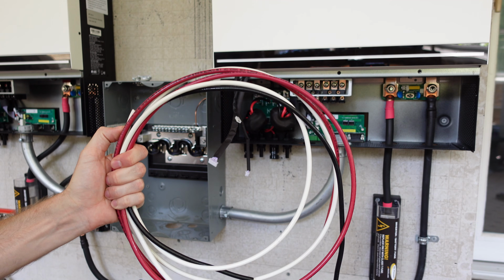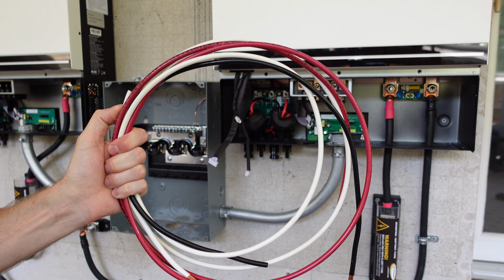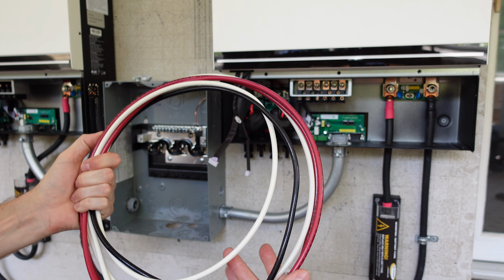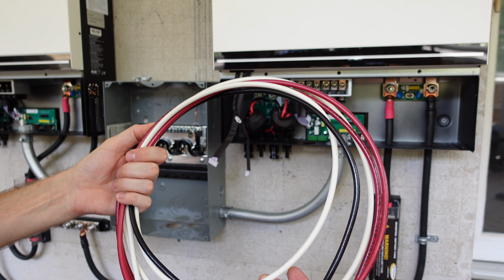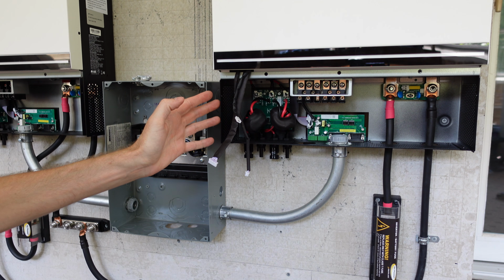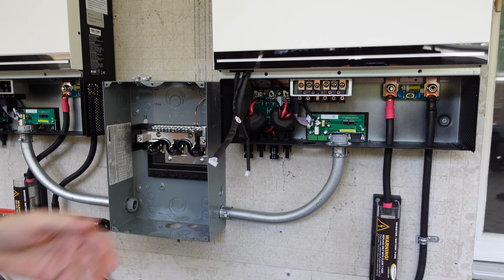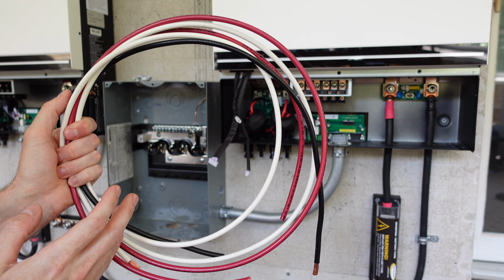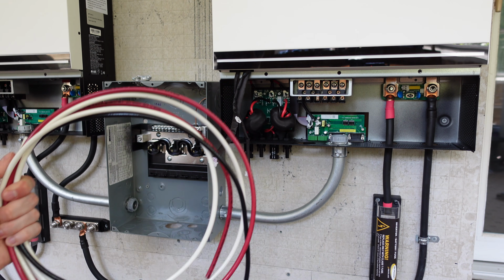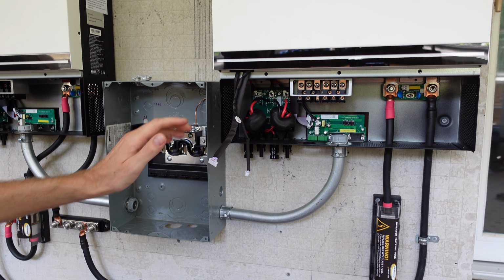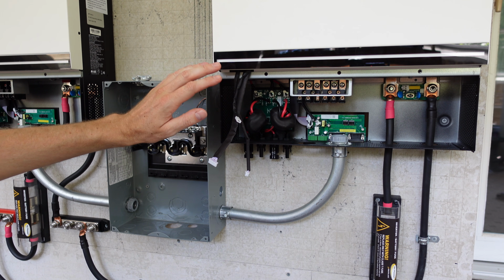For the AC wiring, I'm going to be using this number 6 gauge THHN. This is standard wiring you'd put in an electrical conduit. Now the manual for this inverter does recommend 4 gauge. However, number 6 THHN in an EMT conduit is more than sufficient for the amount of power this inverter is going to be putting out.